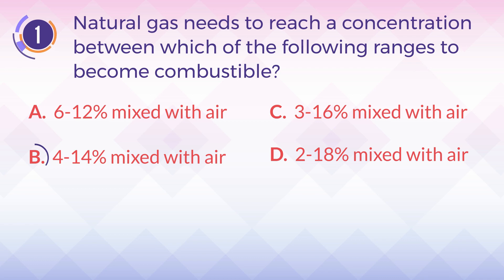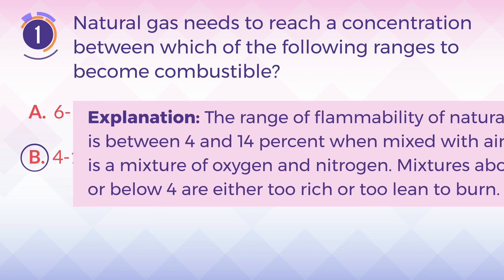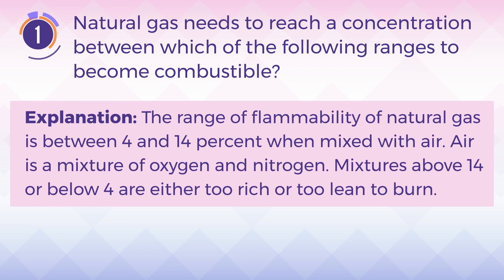The answer is B: 4-14% mixed with air. The range of flammability of natural gas is between 4 and 14% when mixed with air. Air is a mixture of oxygen and nitrogen. Mixtures above 14% or below 4% are either too rich or too lean to burn.